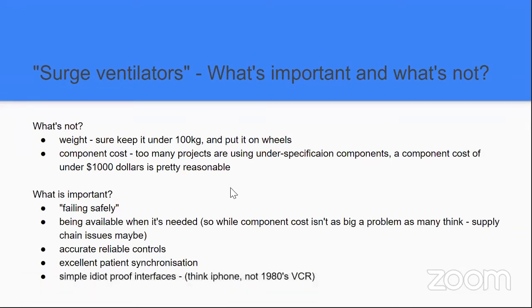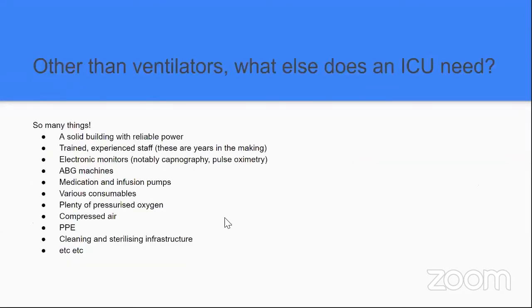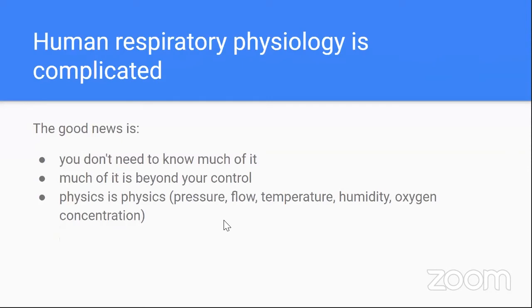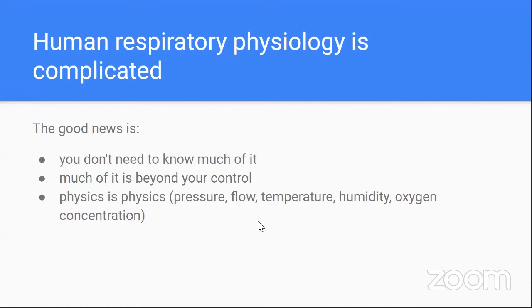A simple, idiot-proof interface is going to be vital, because ICUs will be staffed with people who are either very overworked and tired, or very inexperienced. Beyond ventilators, ICUs need a whole range of other things — it's important we recognize that. Human respiratory physiology is very complicated, but the good news is you don't need to fully understand it. Engineers can control the things they can control: pressure, flow, temperature, humidity, and oxygen concentration. Leave the physiology to the clinicians.